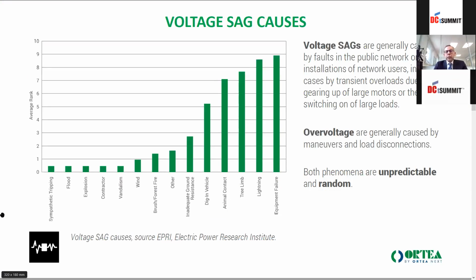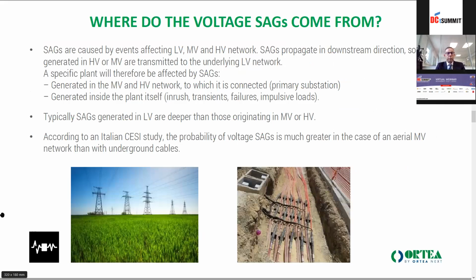So the most important causes of voltage sags are mostly coming from the public network, but they are due to switchings from loads that are very large loads or very big motors on medium or high voltage feeding. So this can create a lot of sags and swells in the line, and some people who are not using such big motors or such big industry and are next to these industries will suffer from these sags and swells and have troubles with production lines or services they have to supply.